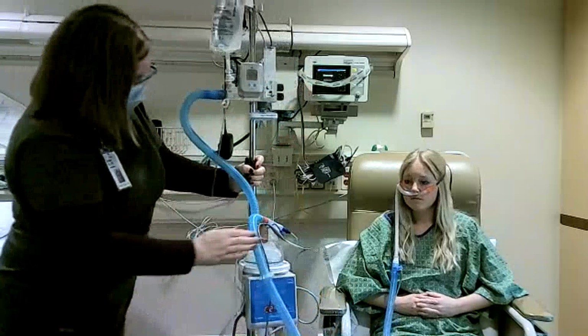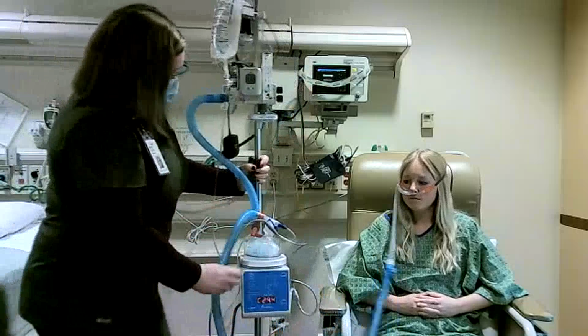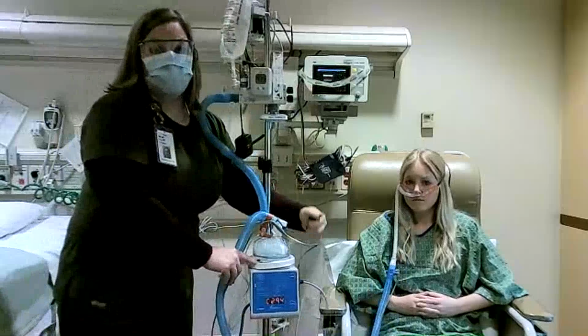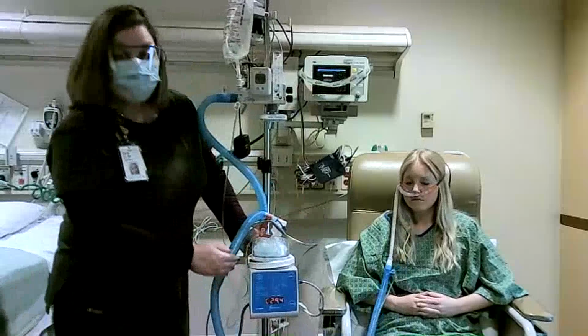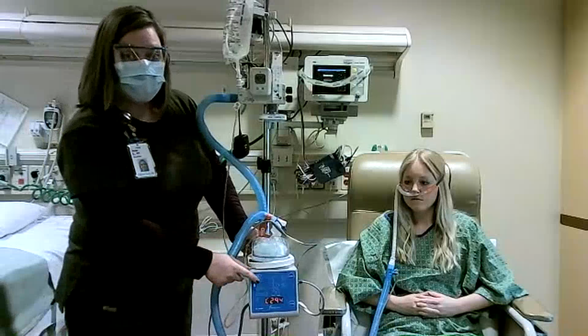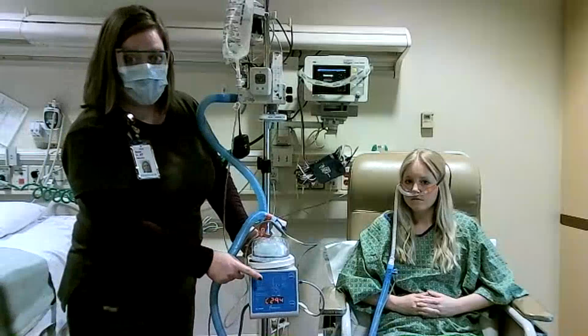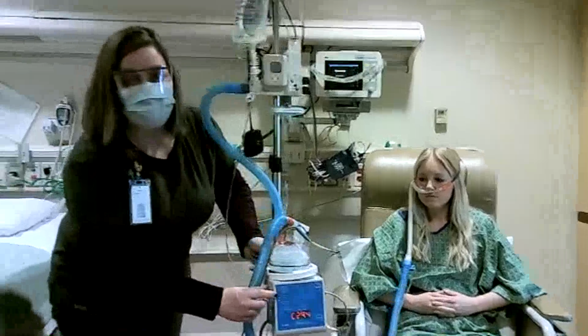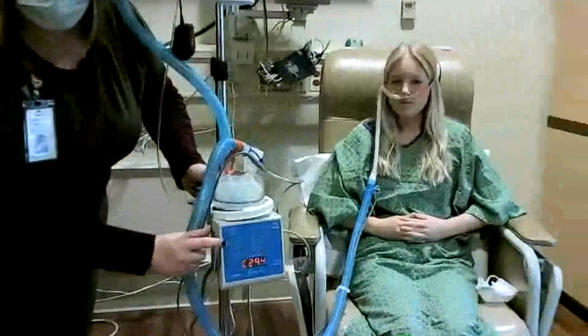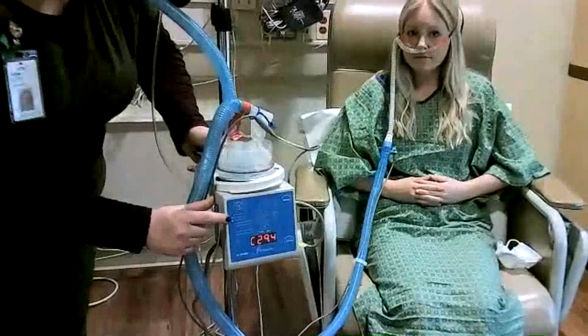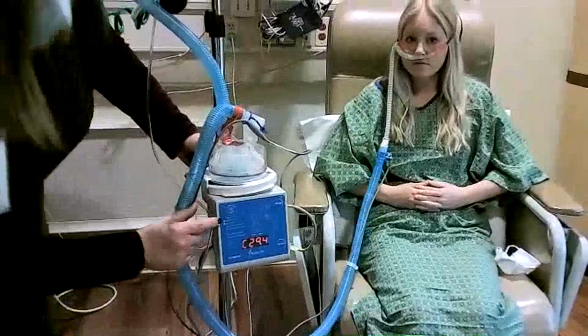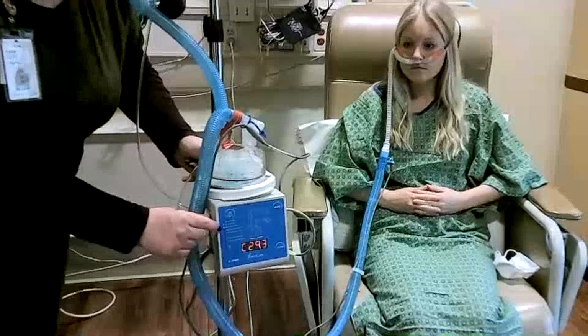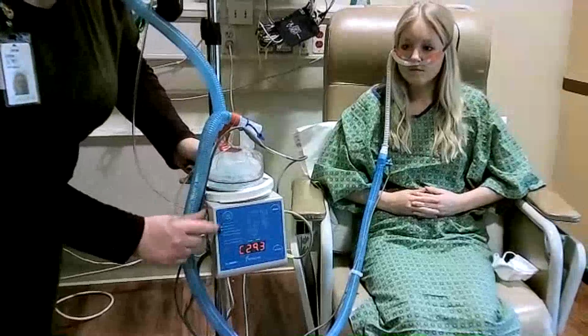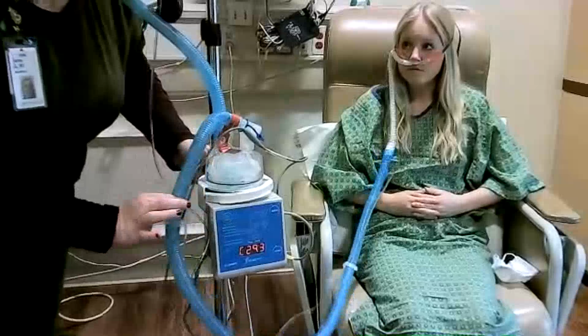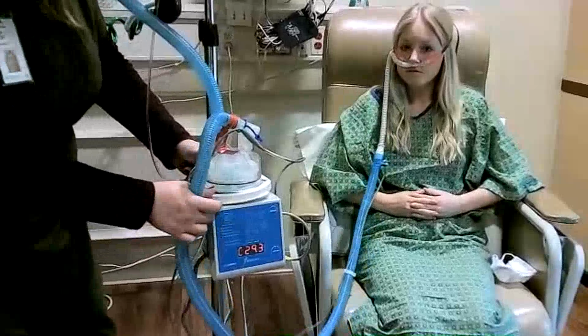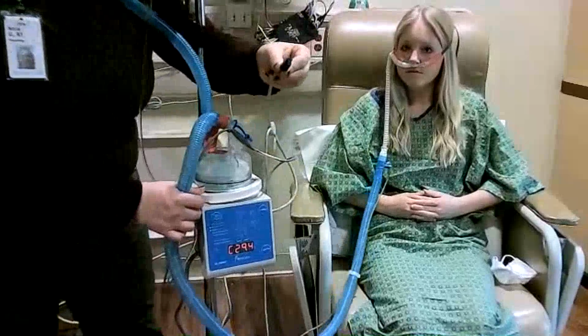If you get some alarms on your heater, you will get an audio and a visual alarm. And so there's your audible alarm. Here's your alarm silence button. You can press that. And then you'll notice here that the lights will light up to tell you why it's alarming. So this one happens to say inspiratory limb, expiratory limb. All it knows is that it's unplugged. It's used to running on a ventilator, so we only have one limb, but it's going to tell you it has a problem with both. And that's because it came unplugged.